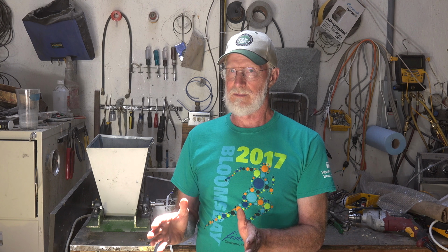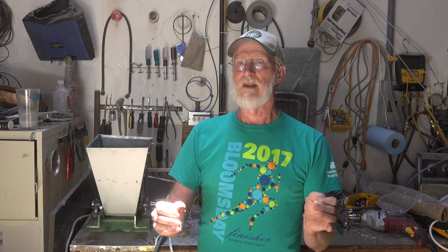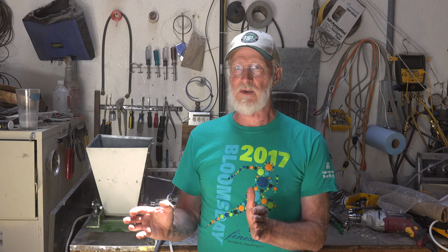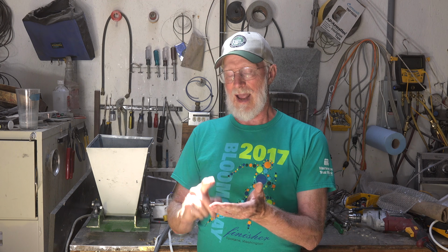There it evaporates. Now here's where we have a little bit of a problem with oil. It doesn't always want to come back unless the conditions are right. So when we turn it into a gas, the refrigerant goes from a liquid to a gas, but the oil stays as oil. So as it's moving through, we need that gaseous refrigerant to be dense enough to bring the oil back with it.